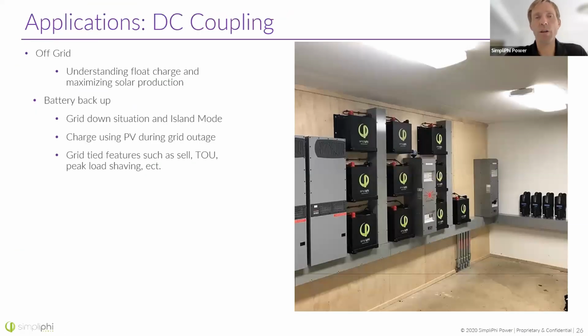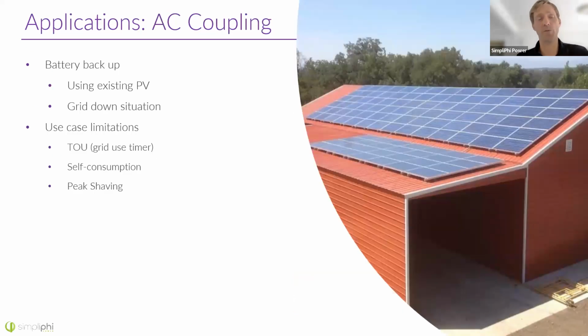There are a lot of examples, and I realize I'm running low on time. There are also examples for DC coupling with off-grid systems. For our batteries with an off-grid system, you can float the batteries in the charging cycle. We have whole trainings on how to float those batteries, or whether you should even float them. The charge cycle has a bulk portion, then an absorb portion where we're topping the batteries off, and float just keeps those batteries at 100%. We don't recommend doing that unless you have a renewable source, and if you do float our batteries, please do so with the 48-volt batteries at 54 volts.